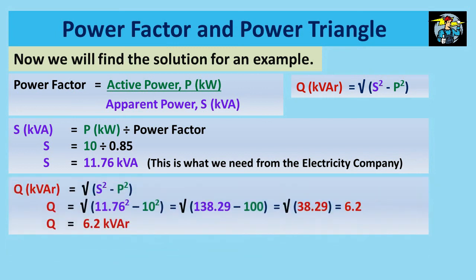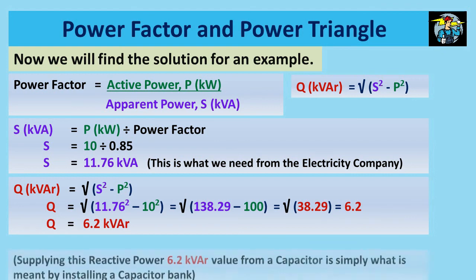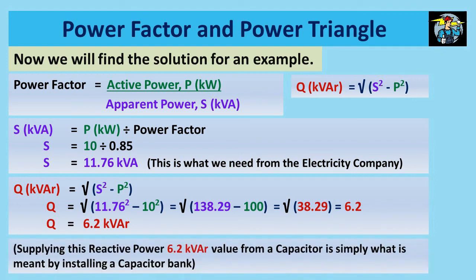To find reactive power Q, we will deduct square of P from square of S first. Square of 11.76 is 138.29, and square of 10 is 100. By subtracting, you get 38.29, and the square root of it is the value of Q. So 6.2 kVAr is the reactive power here in this motor. Supplying this reactive power 6.2 kVAr value from a separate capacitor is simply what is meant by installing a capacitor bank.